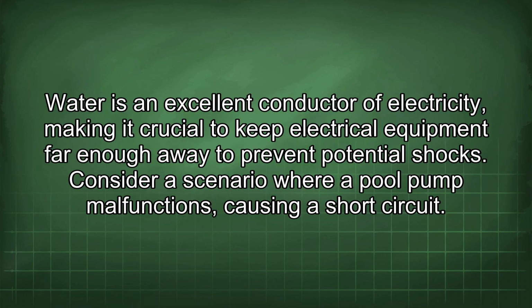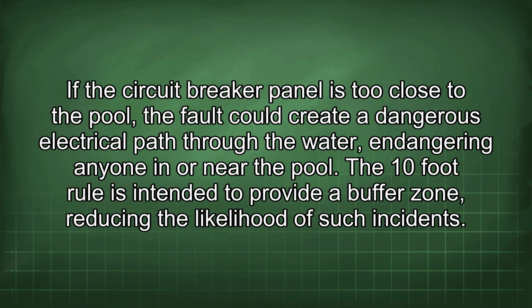Water is an excellent conductor of electricity, making it crucial to keep electrical equipment far enough away to prevent potential shocks. Consider a scenario where a pool pump malfunctions, causing a short circuit. If the circuit breaker panel is too close to the pool, the fault could create a dangerous electrical path through the water, endangering anyone in or near the pool. The 10-foot rule is intended to provide a buffer zone, reducing the likelihood of such incidents.